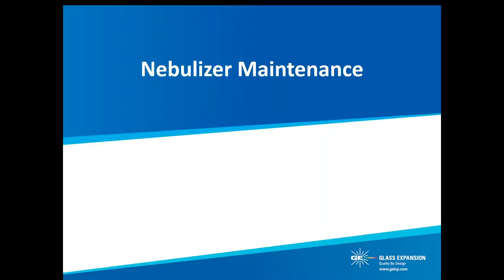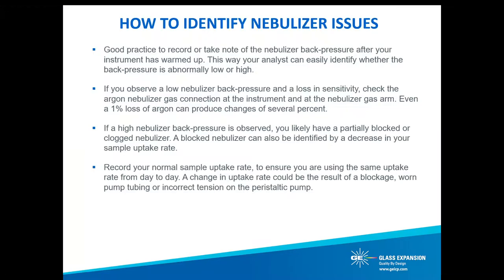Now let's move on to proper nebulizer maintenance. With proper nebulizer maintenance, you can really prolong the performance and lifetime of your investment. Before we get into maintenance procedures, let's briefly discuss how to identify issues specifically related to your nebulizer, which will also help reduce troubleshooting time on unrelated ICP components. Most current ICP instruments have a software feature that allows you to monitor nebulizer back pressure. It's very good practice to record the nebulizer back pressure after your instrument has warmed up when using a brand new or known clean nebulizer, so the analyst can easily identify whether the back pressure is abnormally high or low.